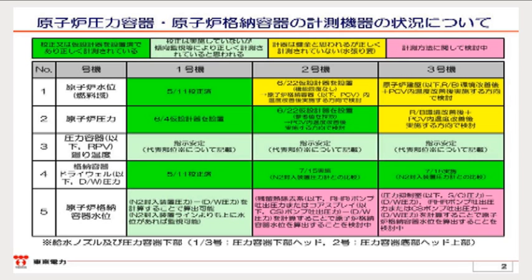Items in yellow indicate that we suppose the measuring instruments are sound, but the data has not been measured precisely yet. And items in pink indicate the summaries concerning the other ways of measuring to be considered in the future. As for the items in yellow, that is, the reactor water level of units 2 and 3 and the reactor pressure of unit 3, we will measure them, and as for the water level of primary containment vessels of units 2 and 3, we are now considering the means for measuring.